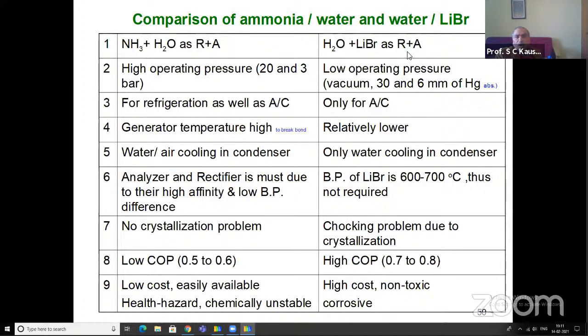But water lithium bromide is suitable only for air conditioning, because water is the refrigerant, we cannot go below 5 degrees centigrade. You can get lower evaporator temperatures with ammonia water as compared to water lithium bromide, where a lower generator temperature is desirable.